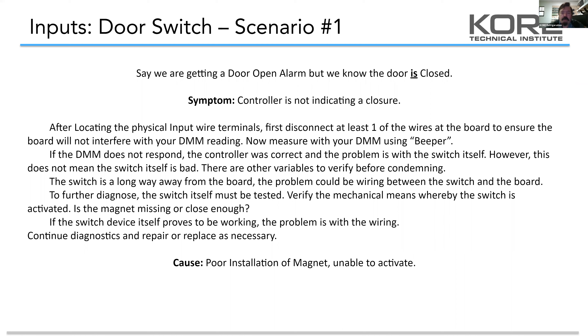Here's a scenario we've had happen several times at Maverick stores. We've got a door open alarm, but we call the store and the store says no, the door is closed. The controller is not indicating a closure. The computer is being called wrong and the control system is at fault because it's not registering a door closure when the door is actually closed. In this case, we've got to do a little bit more investigation. Somebody has got to go out there and properly diagnose what's going on.